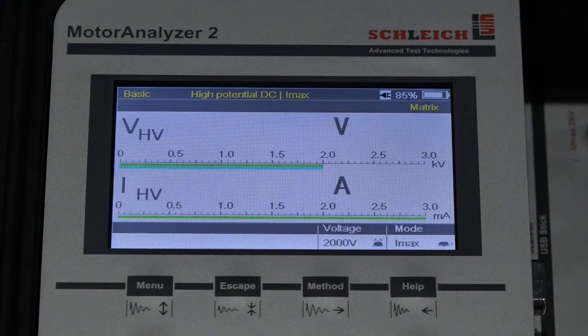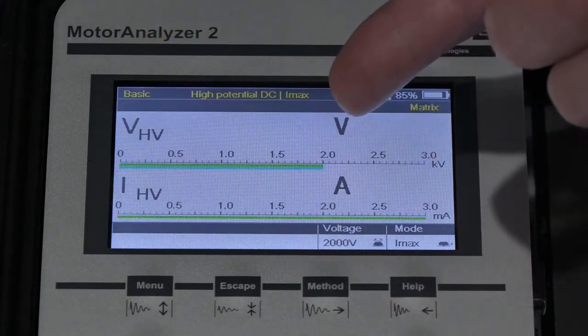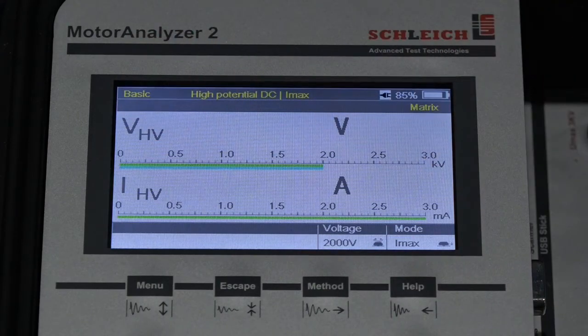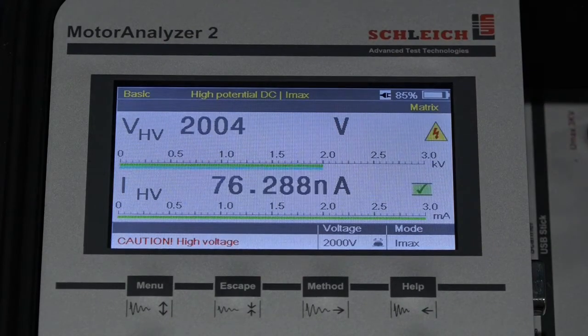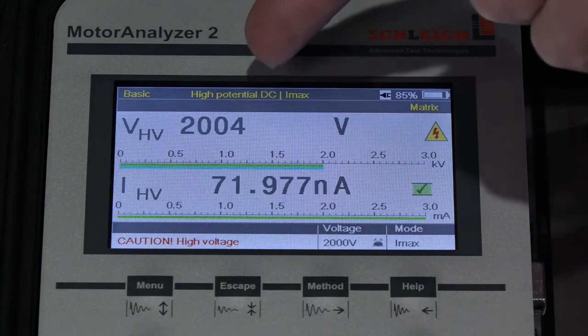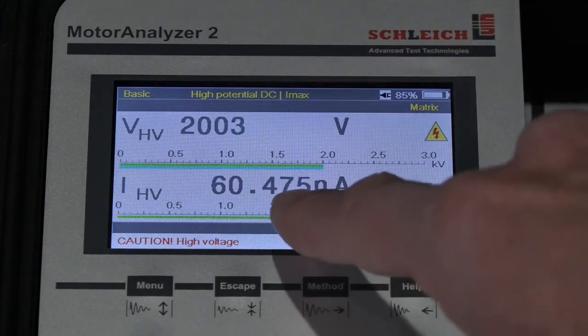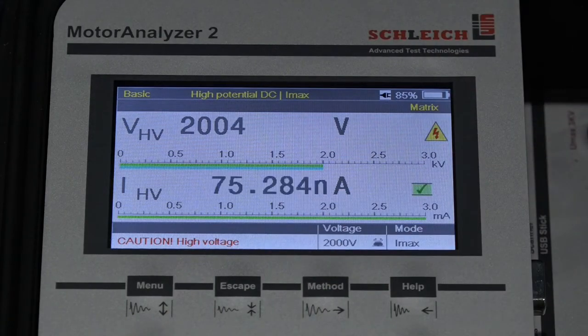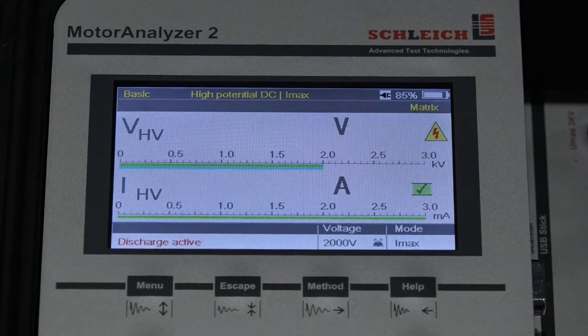Now when I press the start button, it's going to ramp the voltage up to a maximum of 2 kV, and we'll see our current displayed here. So here we go, start button. Ramped our voltage up to 2000 volts. Our indicated leakage current is 60 nanoamps, very low. This is well under a 1/10 of a microamp, so this insulation system is in good shape. To stop the test, press the stop button.